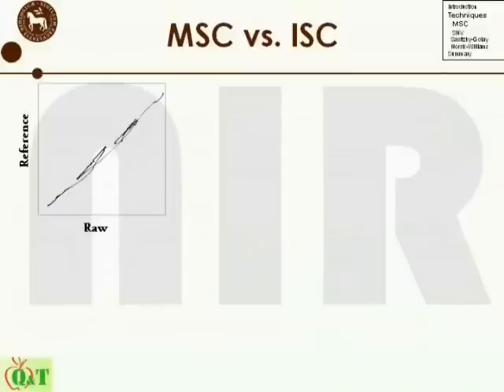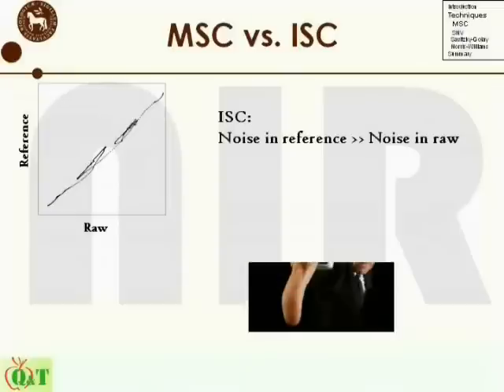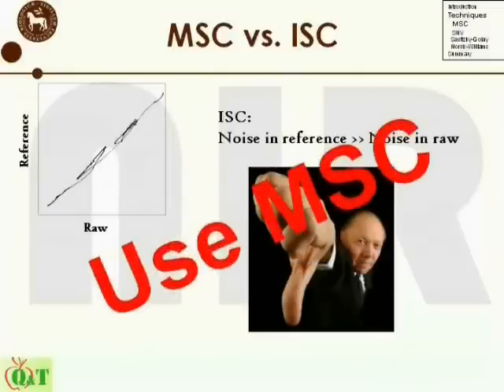Opposed to this, ISC assumes that the error in the raw spectrum is much lower than in the reference. This is never the case if the reference is calculated as the average of a set of spectra similar to the raw spectra, and can only be the case if the reference spectrum was recorded using poorer settings in the instrument or a different instrument altogether. As this is seldom the case, we would not recommend using the inverse version of MSC.